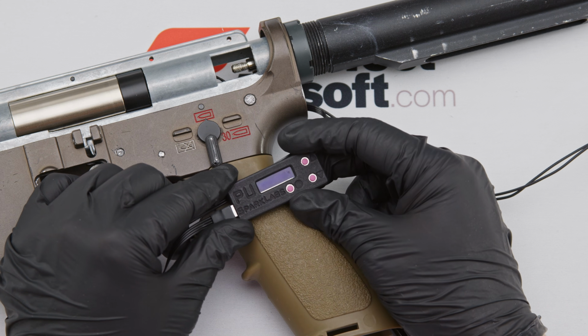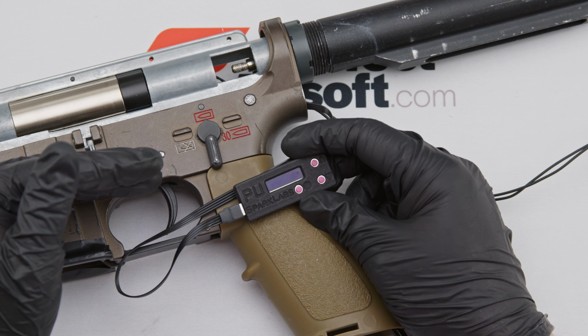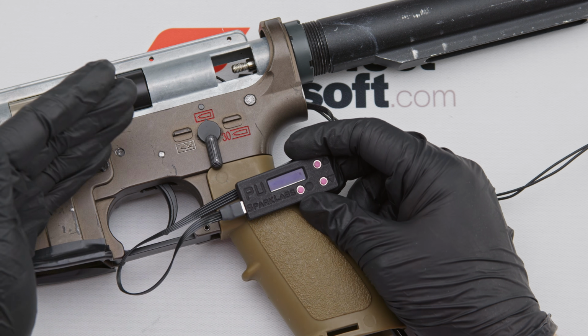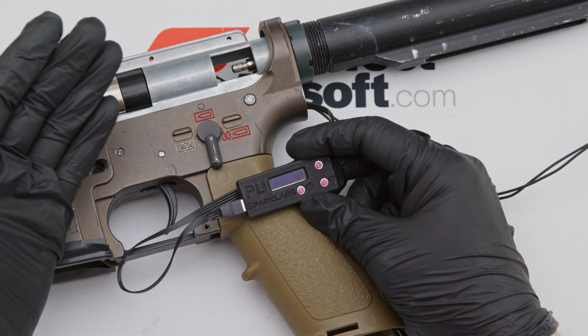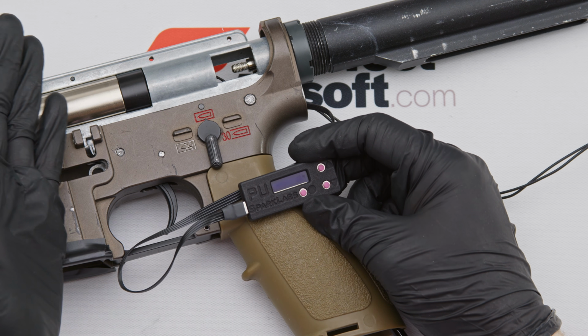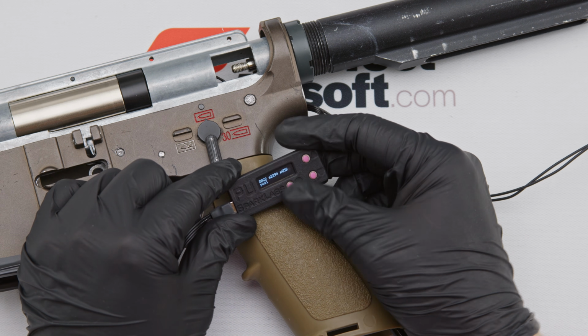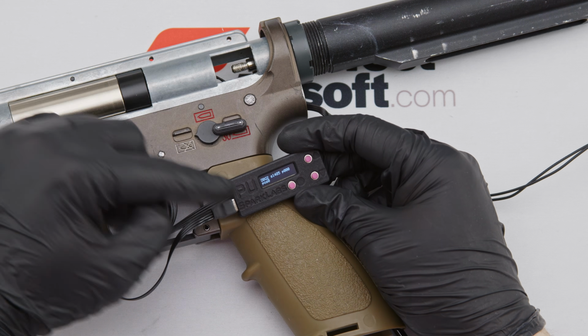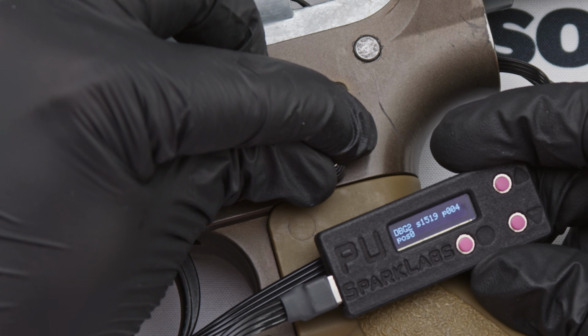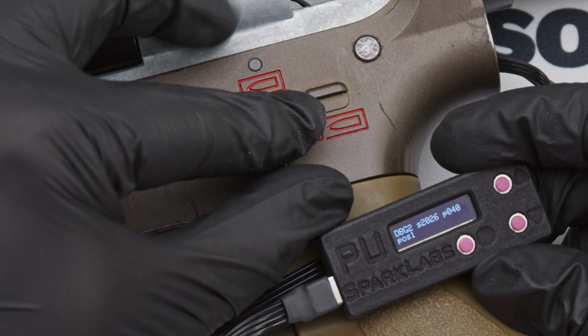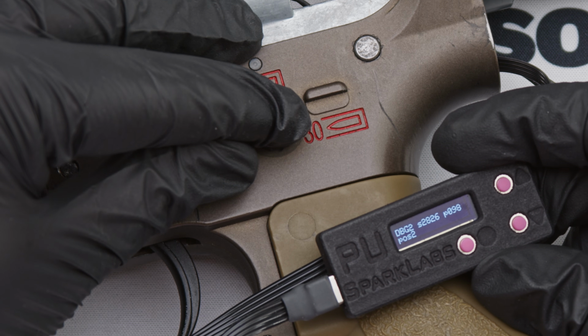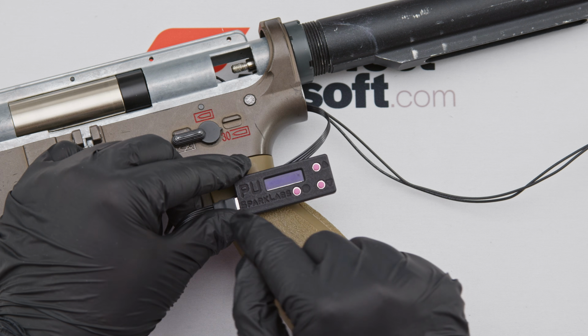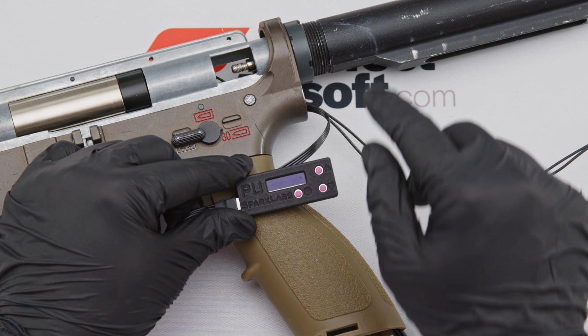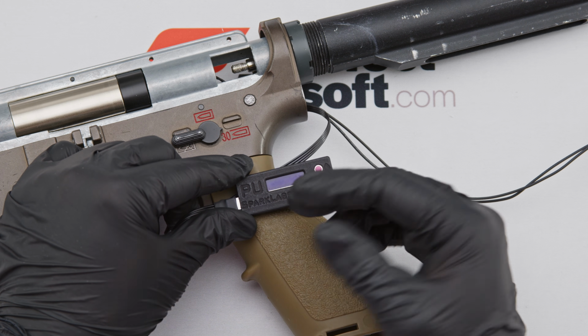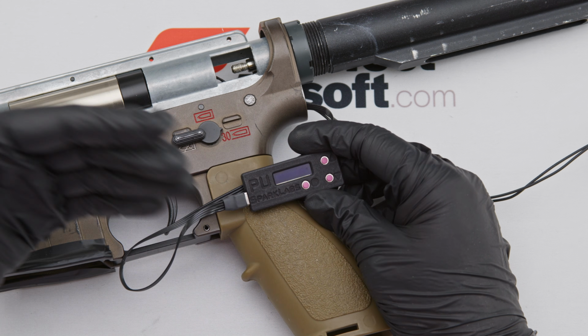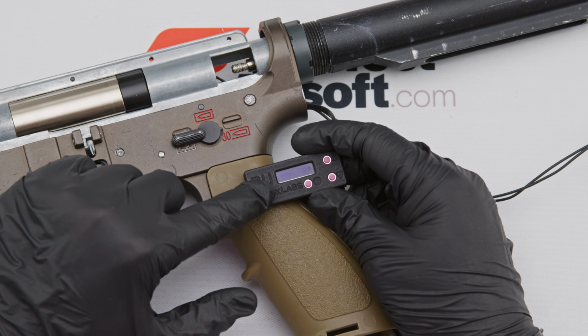There's not a correct or wrong value, but what you want to look for here is that the number moves up and down linearly with the selector plate movement. For example, it should move evenly from 1500 to 3000 when moving from safe to full auto. Let's try that. And I move it slowly, and you can see the second number goes up. If the number moves flat and then up at the end, or even goes up and then down, that means there's probably an issue with the sticker on the selector plate. So it's rather complex, but this is a very good tool for troubleshooting.